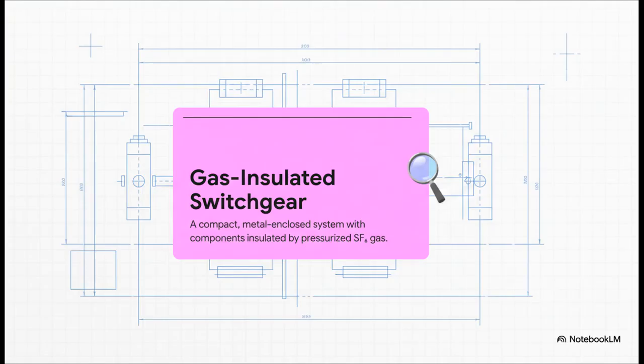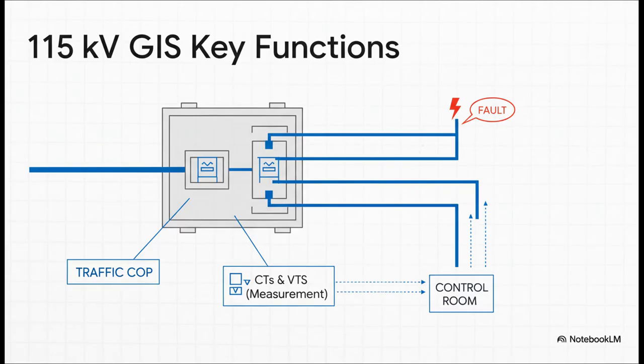And this is it, GIS, which stands for Gas Insulated Switchgear. It's a totally sealed metal-enclosed system. All the critical high-voltage parts, the breakers, the switches, you name it, are housed inside, surrounded by a special insulating gas called SF₆. The biggest advantage here? It shrinks the physical footprint of all this equipment down to a fraction of what it used to be. It's kind of amazing.